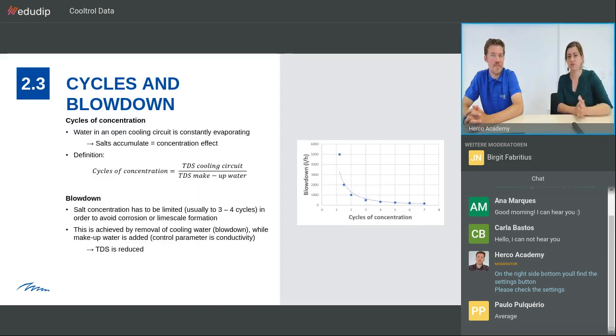Okay, now we come to the definitions really. Cycles of concentration. We're talking now about an open cooling circuit, and water in the open cooling circuit is constantly evaporating, thereby cooling down also the water that remains in the circuit. When water evaporates, we have only evaporation of chemically clean water, so salts and all the other things that might be in the water will not evaporate. Instead, they accumulate and we have a concentration effect. This is called cycles of concentration, and it's defined as the total dissolved solids of the cooling circuit divided by the total dissolved solids of the makeup water. Usually, we would work with about 3 to 4 cycles of concentration in many applications.